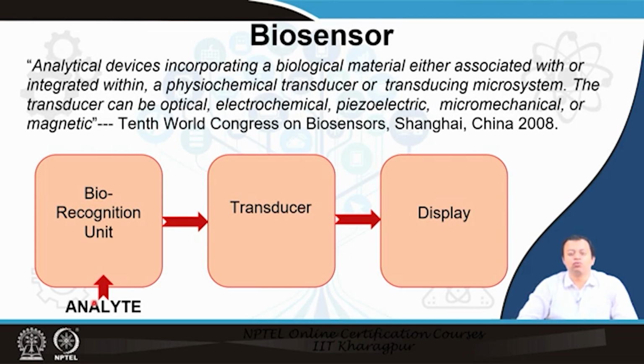So, your pulse oximeter will have no value if it starts changing its value by detecting atmospheric oxygen. Or your blood glucose meter, you just put some amount of sugar onto the material and it spikes up. It has to have a specific reaction, a specific modification upon interacting with the analyte.